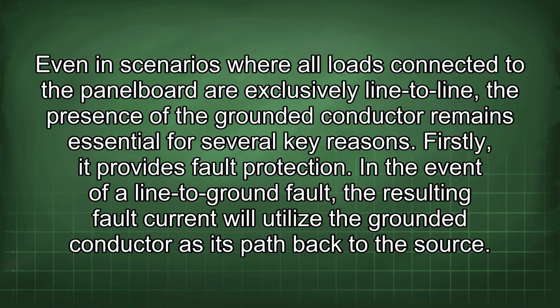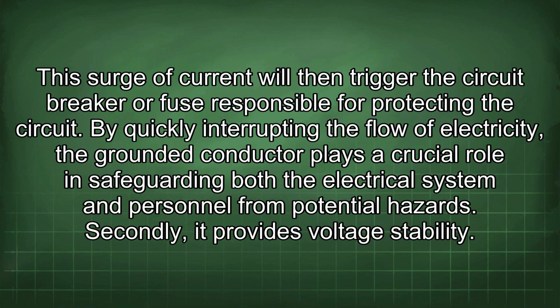Firstly, it provides fault protection. In the event of a line-to-ground fault, the resulting fault current will utilize the grounded conductor as its path back to the source. This surge of current will then trigger the circuit breaker or fuse responsible for protecting the circuit. By quickly interrupting the flow of electricity, the grounded conductor plays a crucial role in safeguarding both the electrical system and personnel from potential hazards.